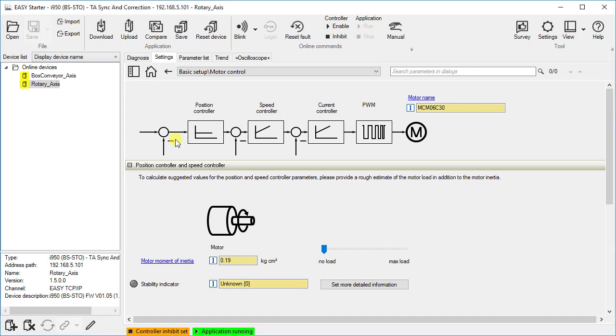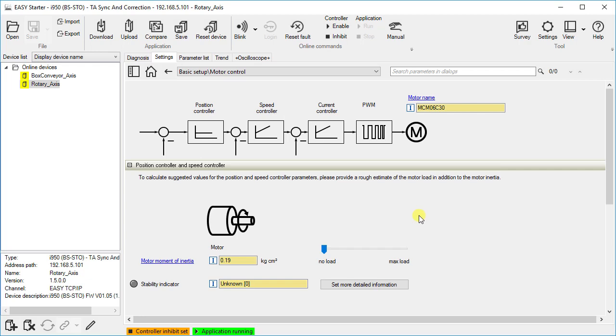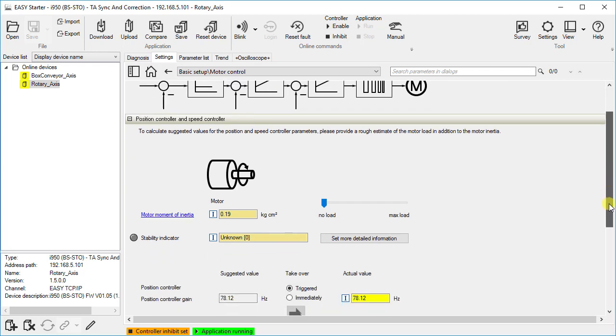In practice, the Ziegler and Nichols adjustment strategy is recommended to optimize the controller settings for speed and position control loops. Ziegler and Nichols determination means that the controller gain is increased until the stability limit is reached. Then the gain is reduced by approximate factor two of this determined value. Using the controller settings determined in this way, the best possible dynamic drive behavior can be achieved, especially with respect to stability, following error characteristics, position accuracy, and behavior when reaching the target position.